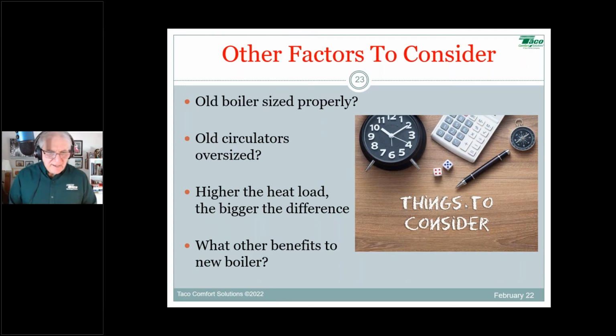Omer asked, would you say a Delta T pump would be better to help boilers get the correct Delta T across that heat exchanger, for more fuel savings? Absolutely. Delta T circulators, like our VT2218, are about the best pump you can put in for the money. It's not the least expensive circulator, but in terms of performance and enhancing efficiency, absolutely.